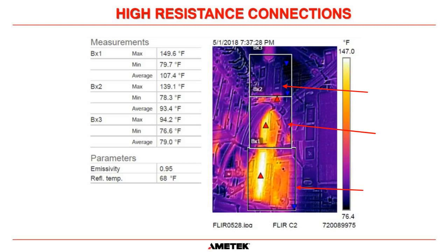So once again, the FSE shut down the UPS in a controlled manner, investigated what had happened, and found that a connection had been made which basically bypassed that top inductor from a circuit. The UPS still operated, but it was operating out with its design, and it only got caught by performing a thermal imaging scan. So two great examples of why performing thermal imaging in a UPS or any other piece of equipment is extremely good practice to find things before they become an actual issue in the future.